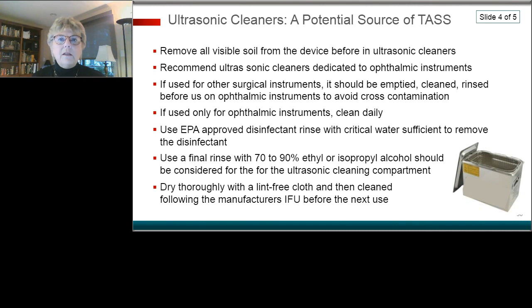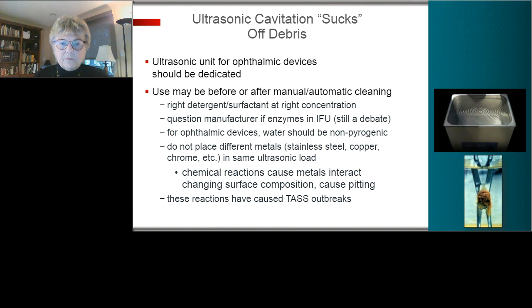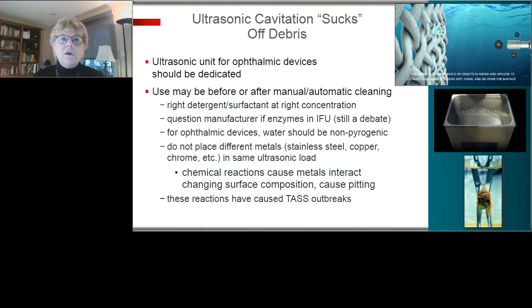Chemical reactions, and we talked about that in general as far as the cleaning, but also when you are putting instruments into the ultrasonic cleaner, you should never mix the metals, because the metals can actually react with each other, especially with the ultrasonic activity going on, so that you'll start to have breakdown and chemical reactions occurring. This is just how it works, which I always think is an exciting little video. Everything that's cut in little tiny areas, the bubble comes in and sucks it out, implodes it rather, and cleans areas that we can't otherwise clean. So it's a very, very important piece of equipment.